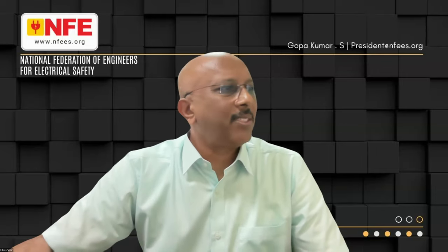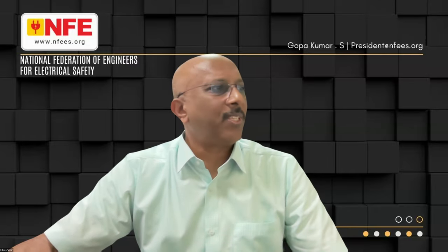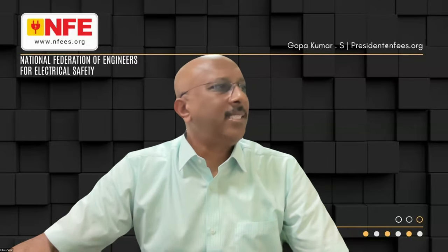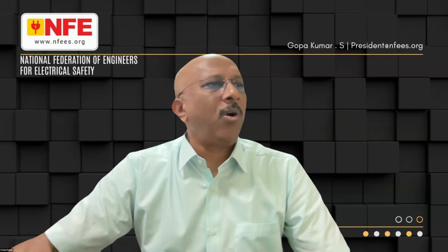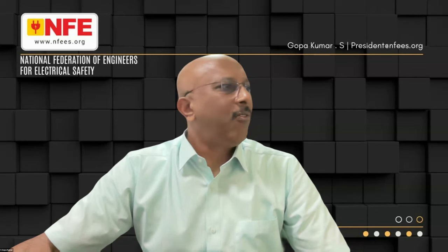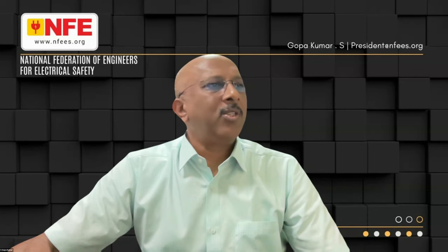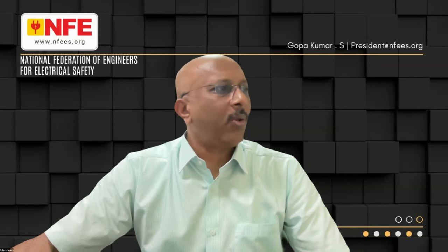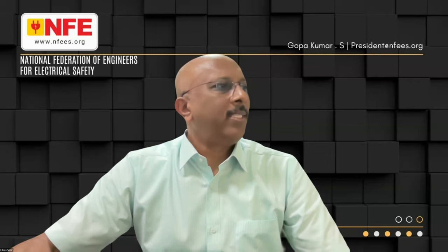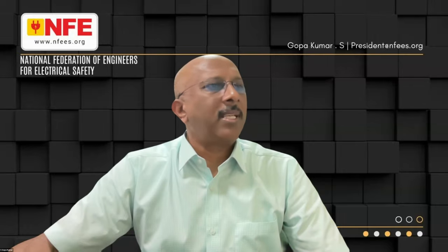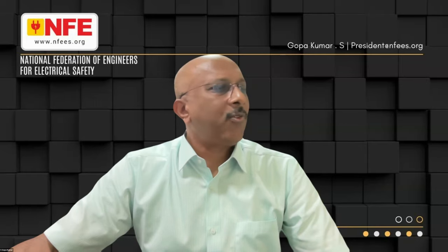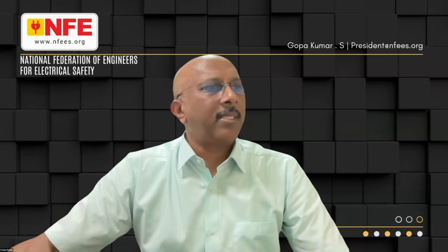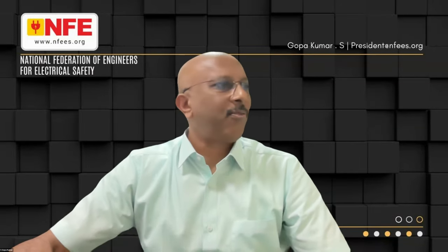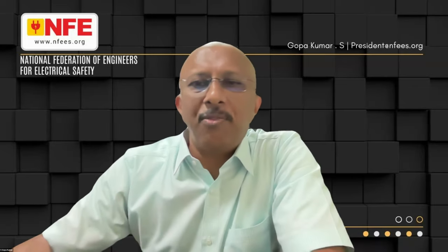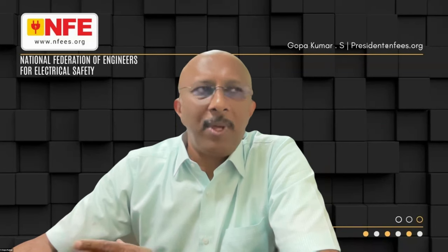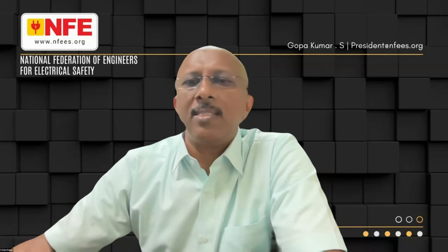The speaker reads from the standard: the arc can be considered so low it likely won't cause permanent injury, and in certain cases incident energy is low enough that arc flash protective equipment isn't required. For example, when voltage is under 400V AC with short circuit current at or below 1 kiloampere, or under 400V AC/DC with upstream fuse rating at or below 63 amperes, or voltage under 50V AC or DC. Participants are directed to Annex C for details.